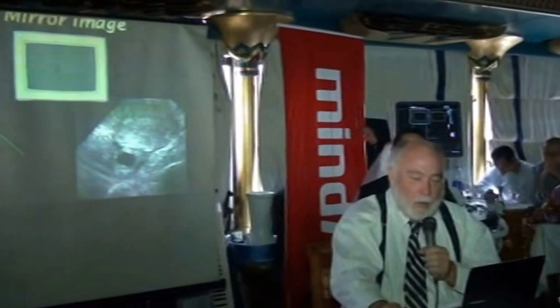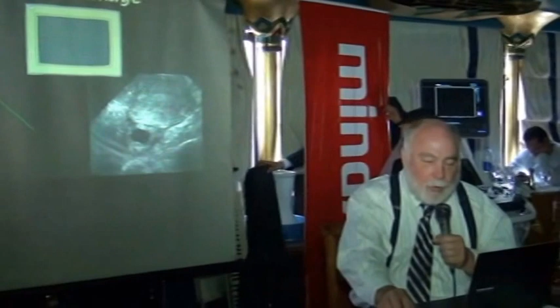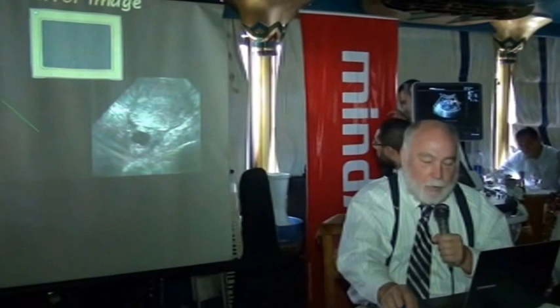Mirror image. Here we have the transducer and the beam, and it hits a reflector, but the reflector is not perpendicular to the beam. So the reflector sends another beam to somewhere else in the body. And here it sends to this green screen here. So the machine gets the yellow echo coming from the red interface, puts it in the right place. But then the beam that has gone to the green and then back to the red and back to the transducer is placed as a second dot on the screen. Now the machine doesn't know that the beam has been deflected to the side like this. The machine simply supposes that the beam comes from deeper inside the patient and places the image deeper. And that causes some artifact like this one here. Fortunately, the image is a bit off from the screen, but you see her uterus, you see an ovary with a follicle, and there behind is a second ovary with another follicle. That second ovary does not exist at all. It is simply a mirror image created by the machine.